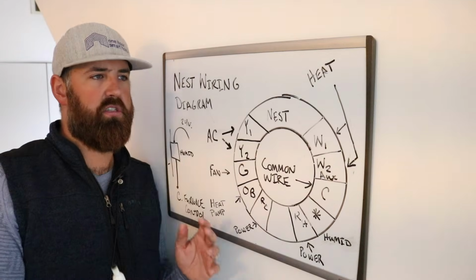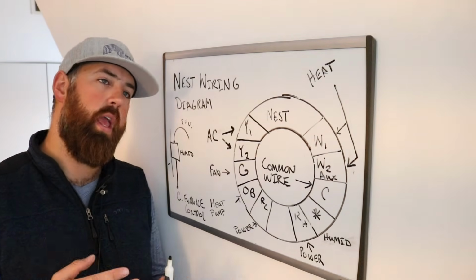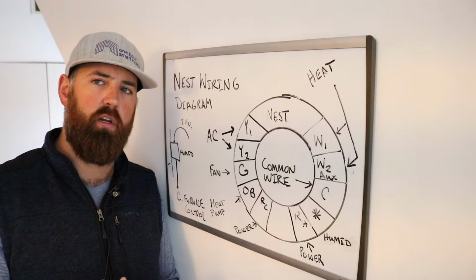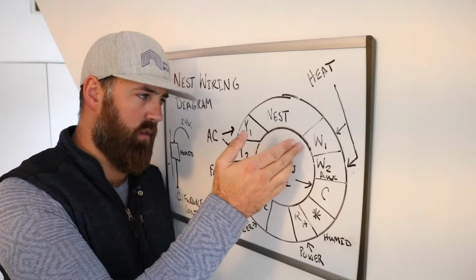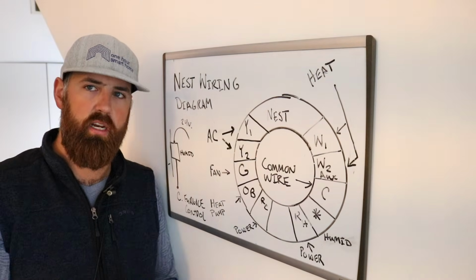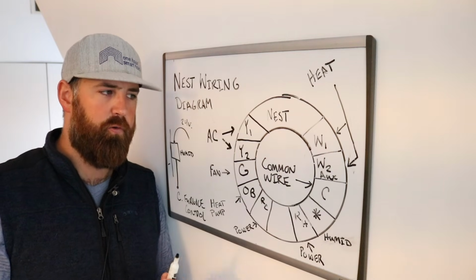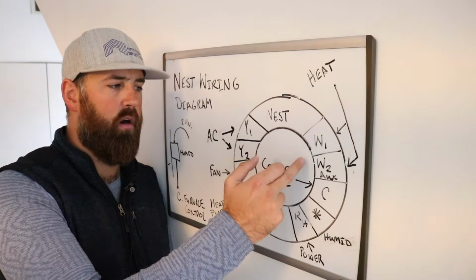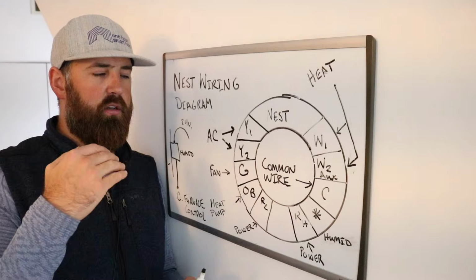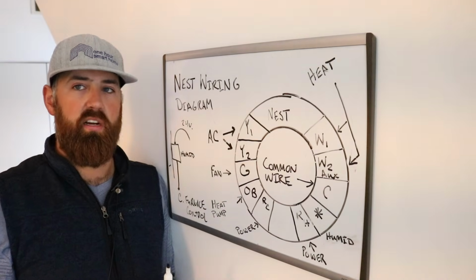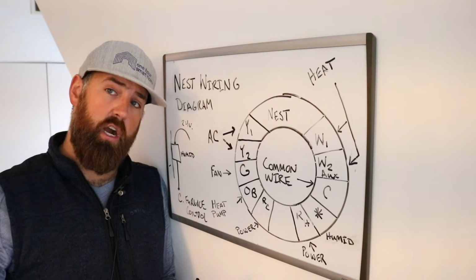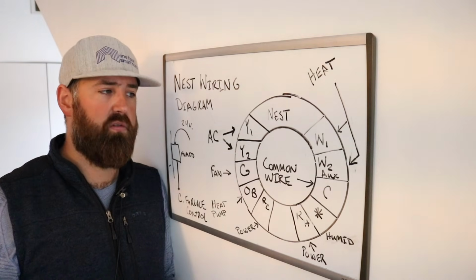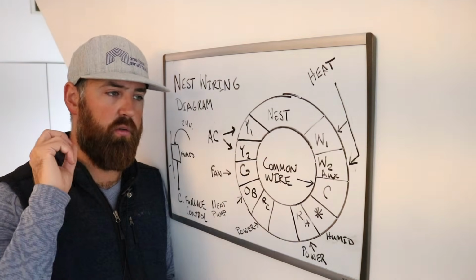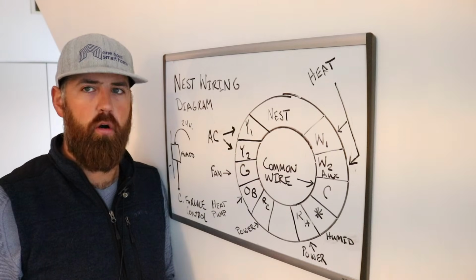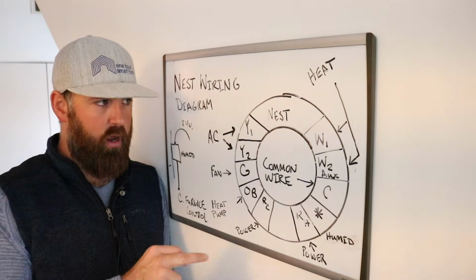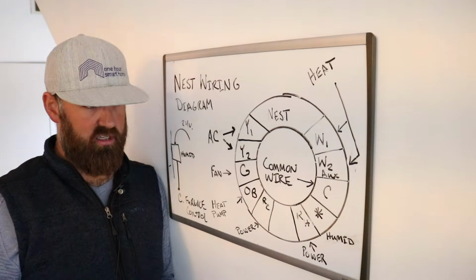If you've got a newer system with more features, you might have 2-stage heating. What 2-stage heating does is give you a low power for heating and a high power for heating—you're burning more fuel in the high power W2 stage. If your house is really cold, it lets your house get warm really quick: with 2-stage heat, it'll go all the way up to high power, blow a ton of warm air through the house, and you'll heat up quicker than you would with just W1.